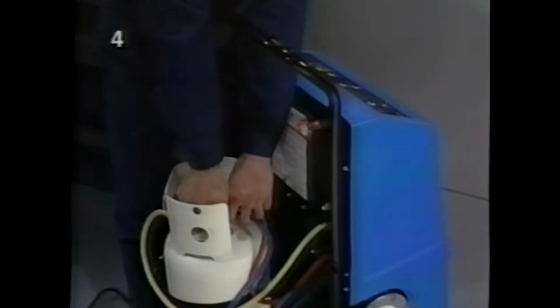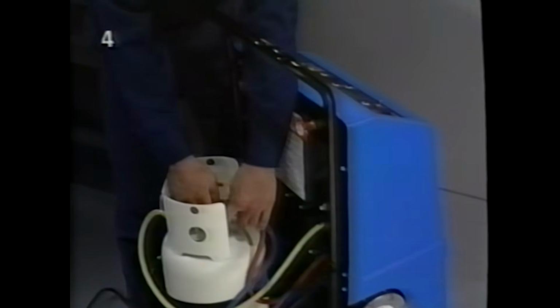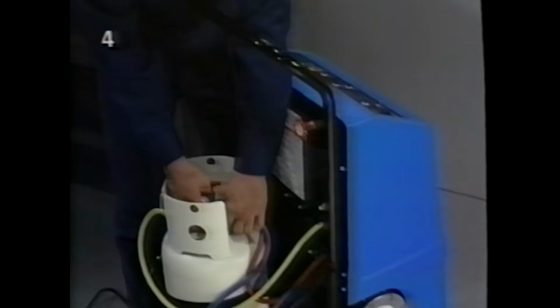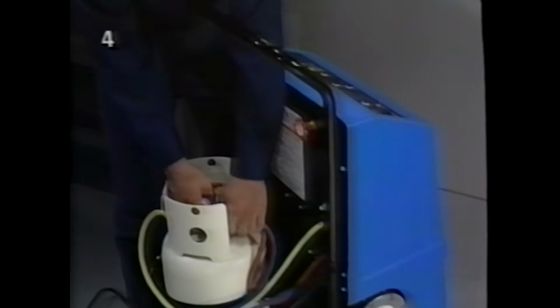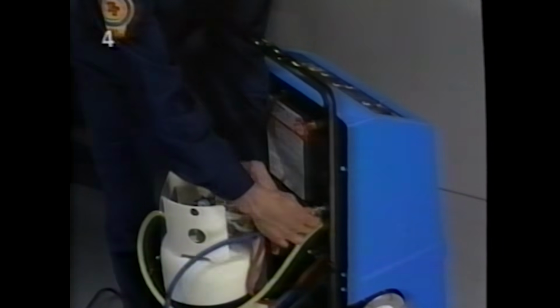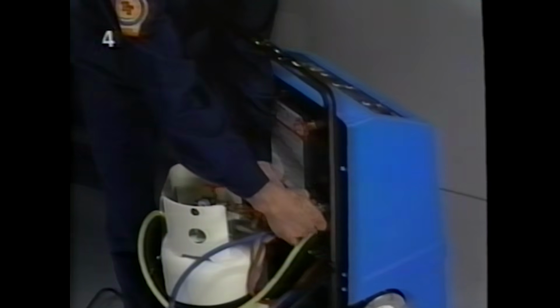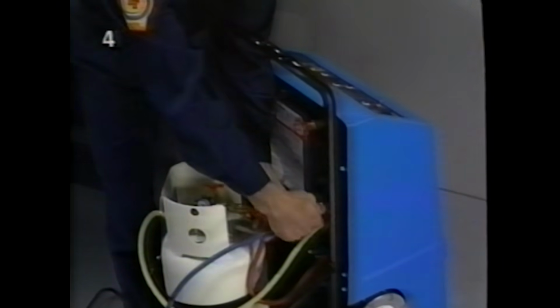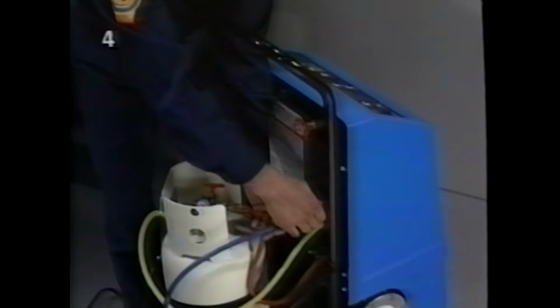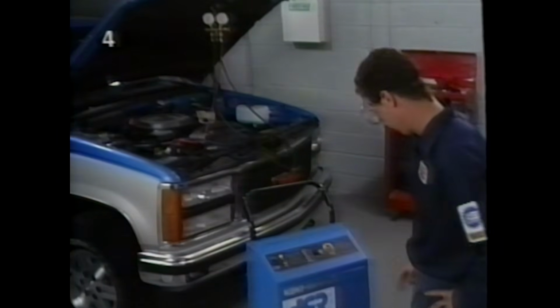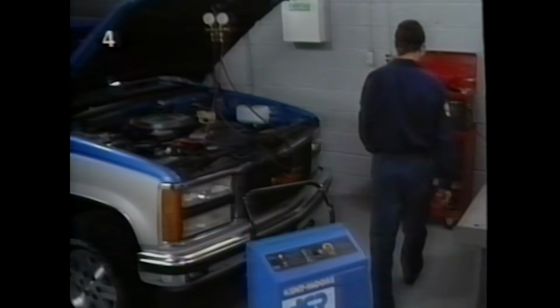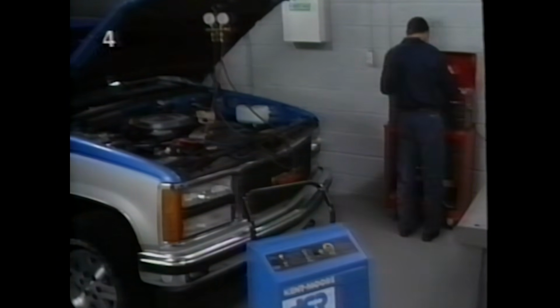Close the liquid valve on the storage tank and connect the blue hose to the recovery station inlet. This step and the one that follows are absolutely critical to avoid releasing R12. Serious injuries, including blindness and death, have resulted from contacting or inhaling liquid refrigerant. Start up the compressor to pull all the refrigerant from the ACR3 into the storage tank. The compressor will turn off by itself. Now it's safe to open the filter.